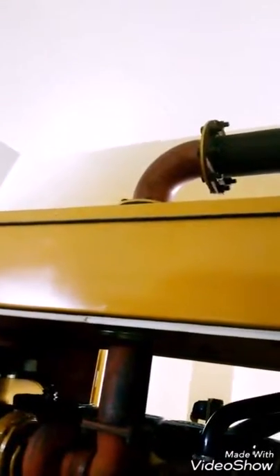Walk around the generator. This is your stack on top, your exhaust stack. All your burnt fuel will pass out the top and out the exhaust, outside the generator room. The shroud is at the top. The hot air from the engine goes out the top of this generator. We take a quick look. Your fan blows all the air up through the top of this casing. Some generators, it will blow it through the front. This one goes through the top. We have our vents here, carrying everything out.